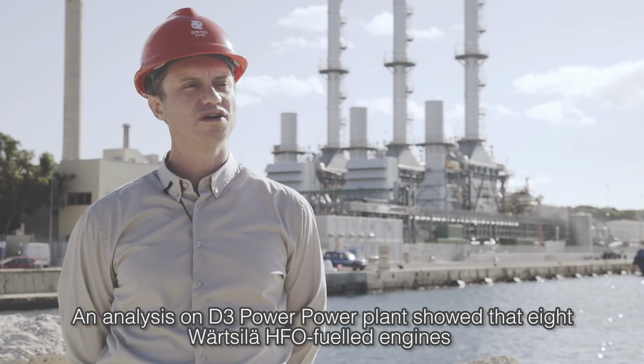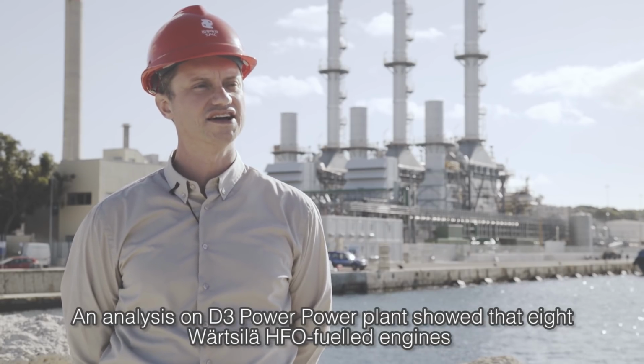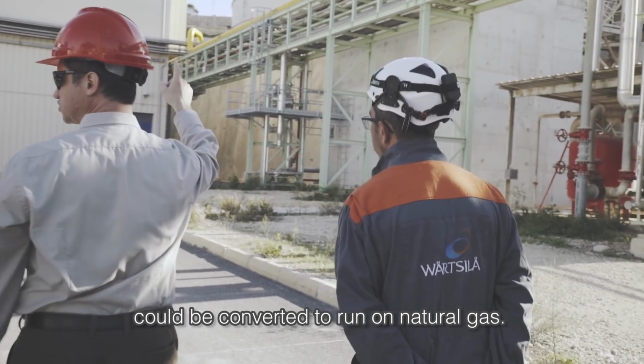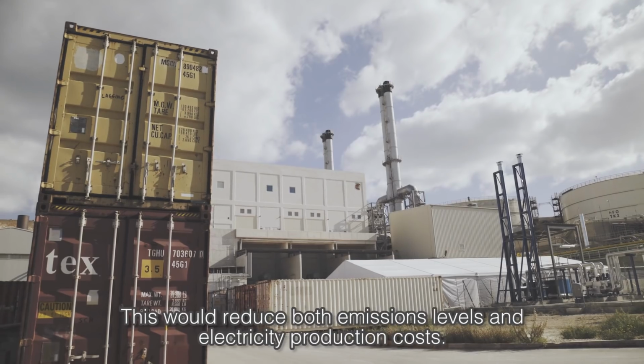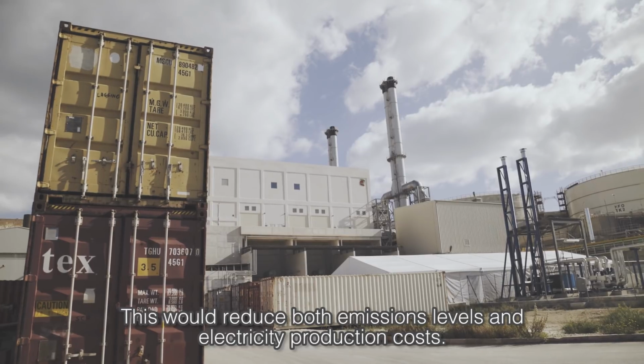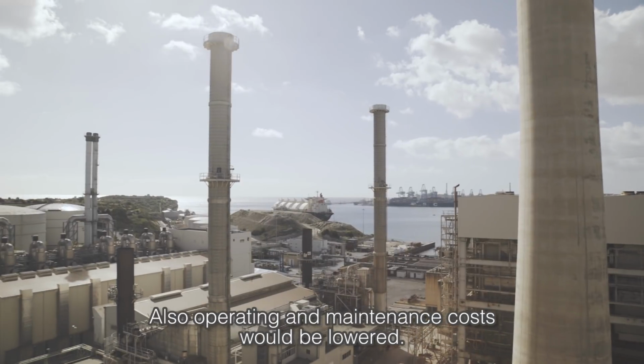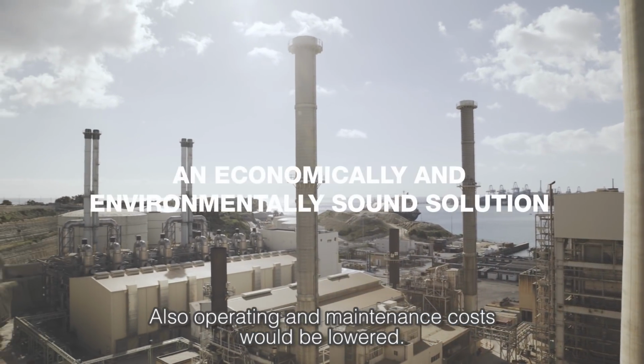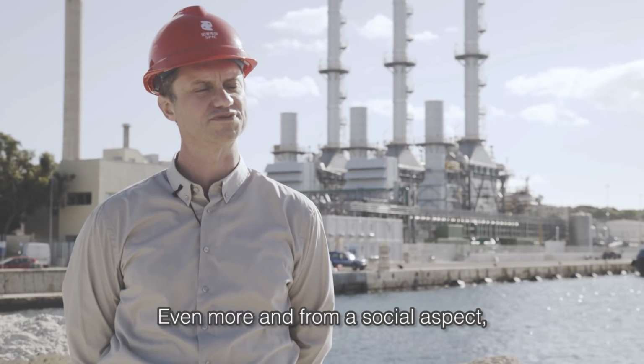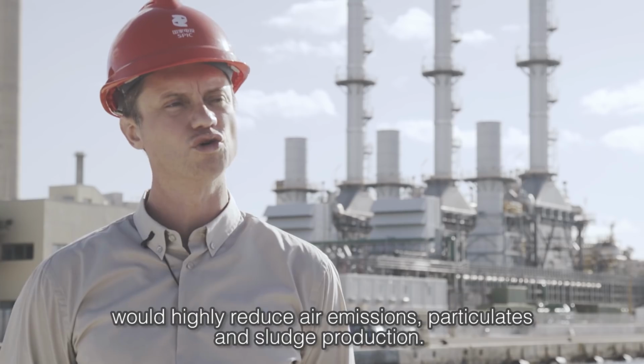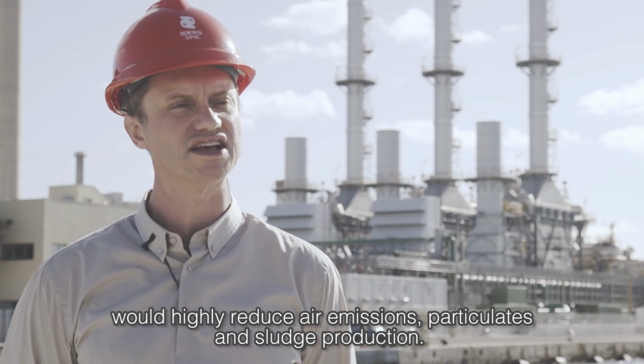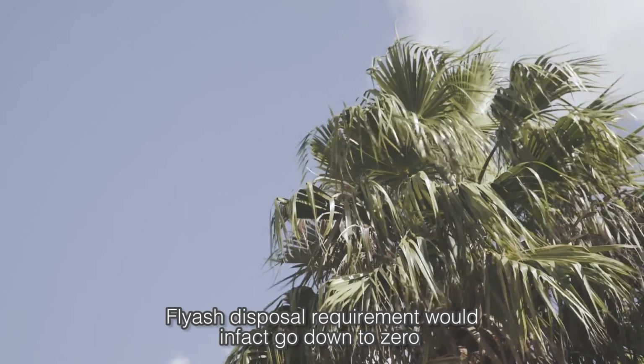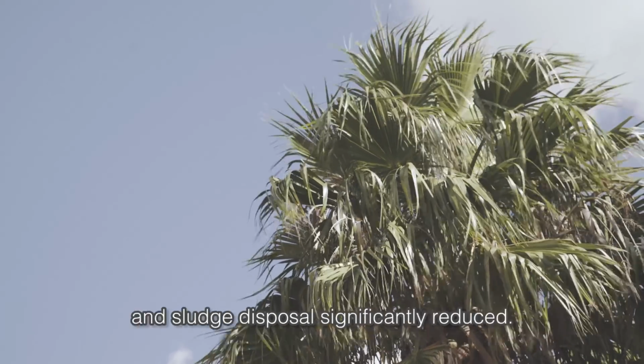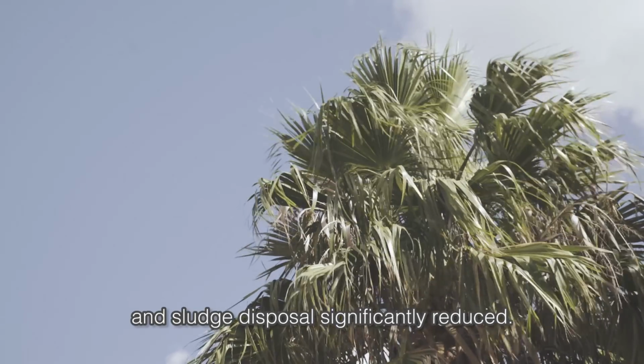An analysis on the power plant showed that 8 Wärtsilä HFO-fueled engines could be converted to run on natural gas. This would reduce both emission levels and electricity production costs. Also, operating and maintenance costs would be lowered. Even more, from a social aspect, running on natural gas would highly reduce air emissions, particulates and sludge production. Fly ash disposal requirement would in fact go down to zero, and sludge disposal would be significantly reduced.